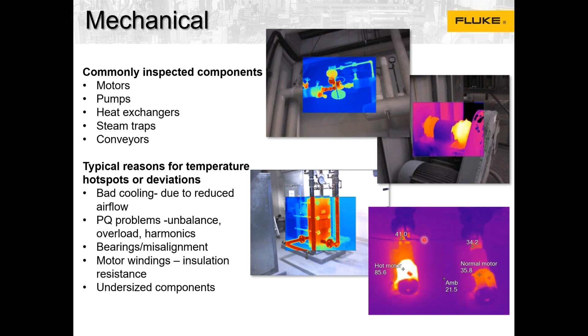So you need to check the nameplate or even the manufacturer data sheet for the highest temperature that the motor can allow. So let's say the maximum temperature of the motor is 90 degrees, and we are measuring the surface temperature. To understand the internal temperature, you need to add 10 degrees or even 20 degrees depending on the class of your motor. If you add 10 or 20, it can exceed the manufacturer recommendation, and this will affect the winding and the insulation of your motor, because just a 10 degree rise in the temperature of your motor can reduce the motor life by half, and typically it will be the insulation failure.